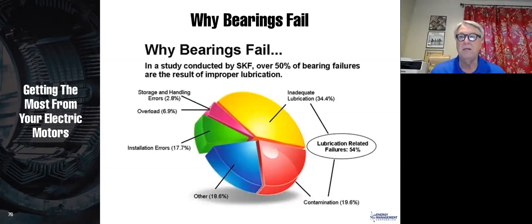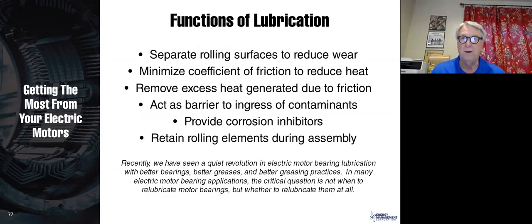This is from SKF, a bearing manufacturer. It shows some of why bearings fail, and they're saying that lubrication failures are responsible for most bearing failures, and bearing failures are the number one reason for motor failure. These are functions of the lubrication. You can just try to scan that, and again, you will get a copy of this, or you can download a copy of this once we post it online.